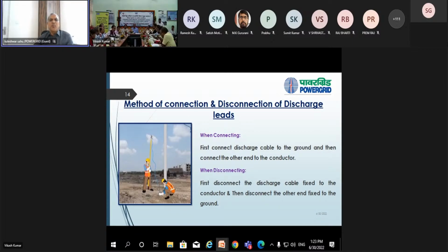Method of connection and disconnection. This is most important. Most accidents are caused during the connection or disconnection of earthing. So when we are going to discharge particular equipment for doing some work, first we have to connect the discharge cable to the ground, and only then connect the other end to the conductor. This is the sequence when we are earthing, discharging any equipment, and the reverse vice versa. When disconnecting, first disconnect the discharge cable fixed to the conductor, and only then disconnect the other end fixed to the ground, to avoid any accident.